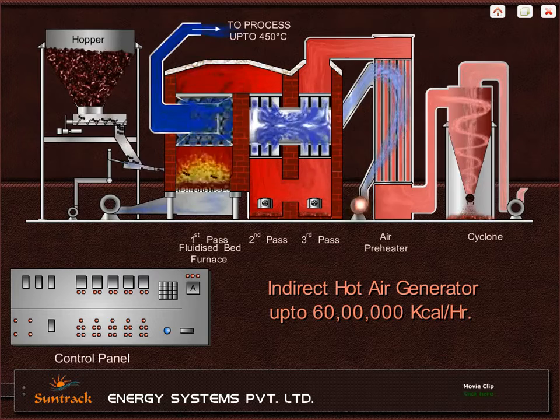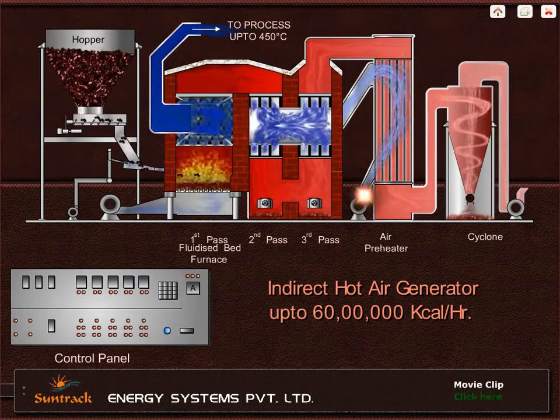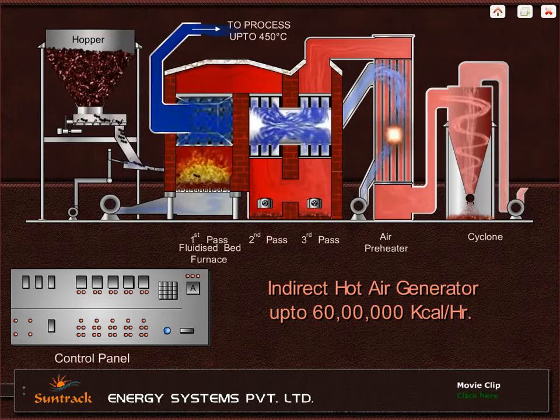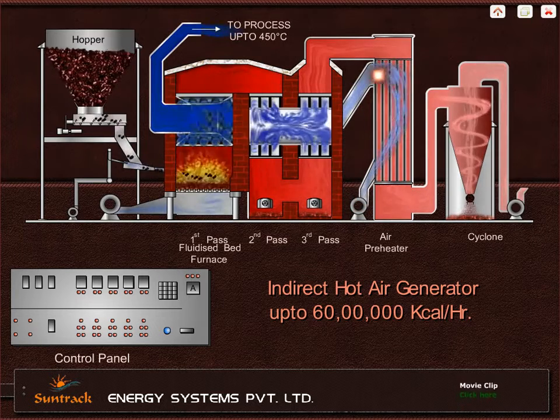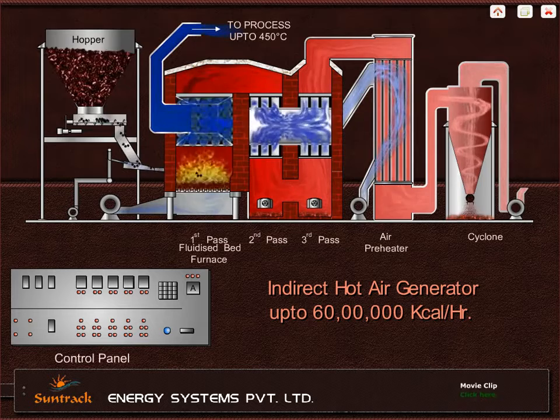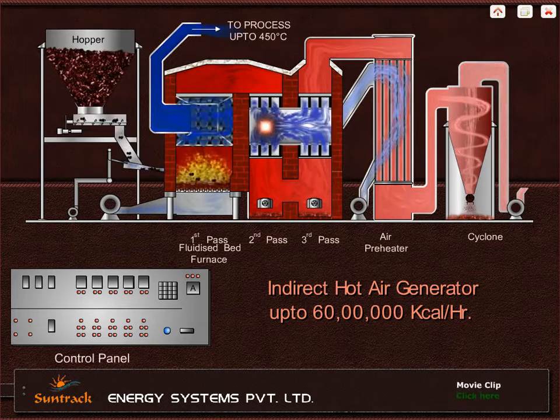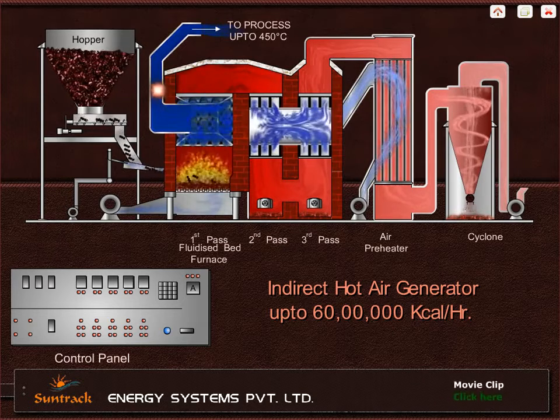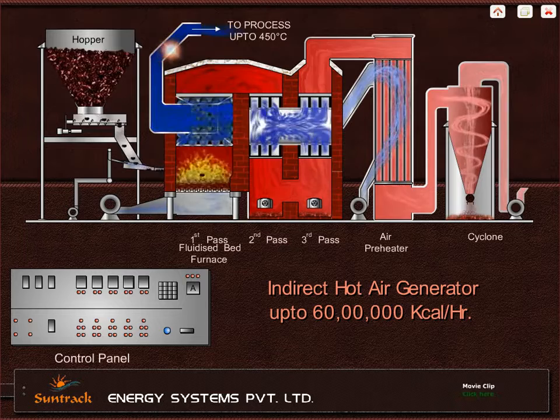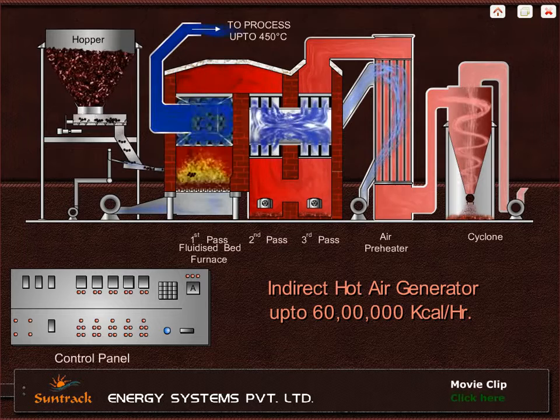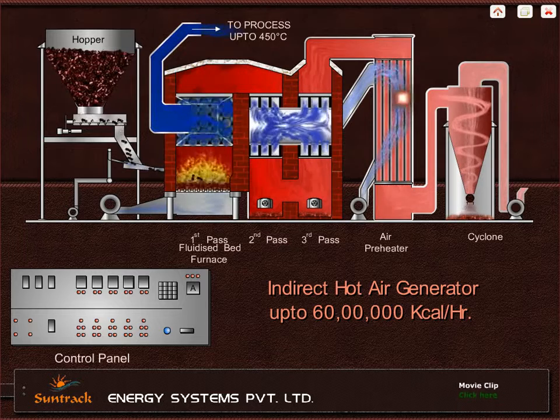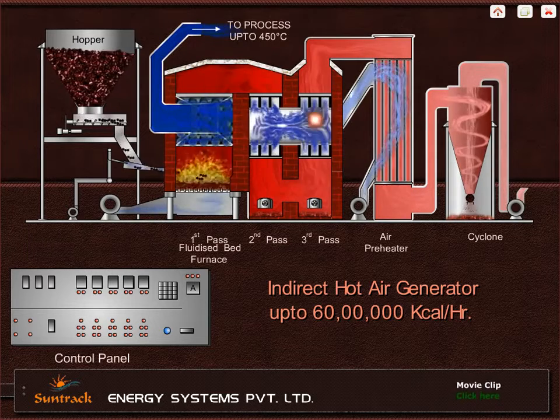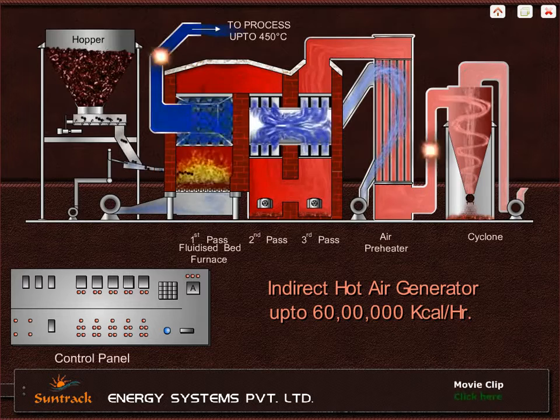Clean air from the atmosphere is drawn by the clean air fan and blown to the air preheater where it gets heated up, then passes through the third pass, second pass, and first pass before leaving the system for process requirements. Clean air is heated counter-currently by combustion flue gases to achieve higher efficiency.